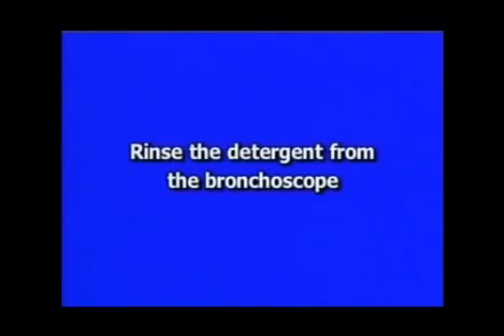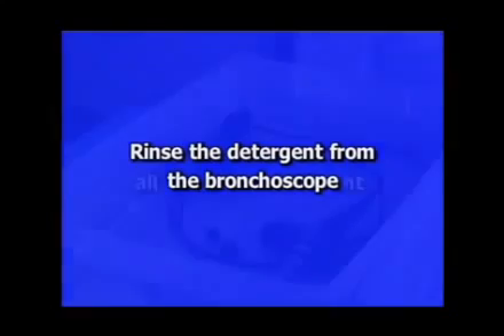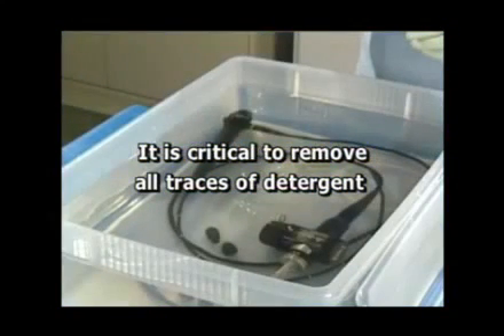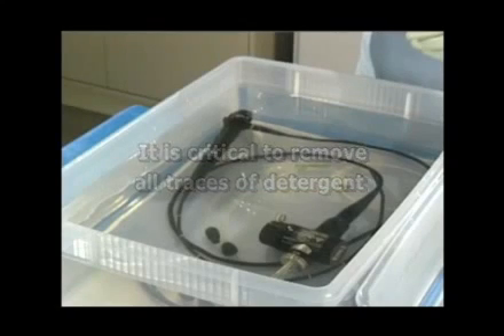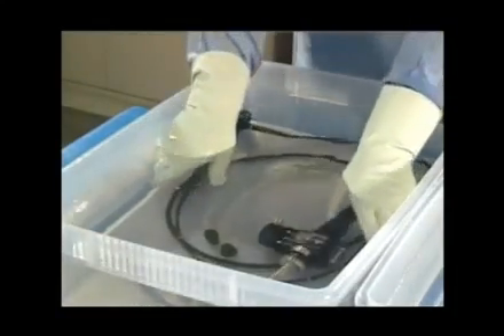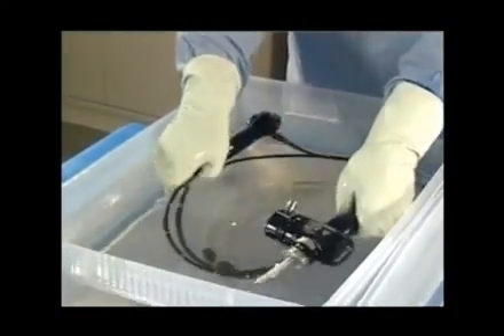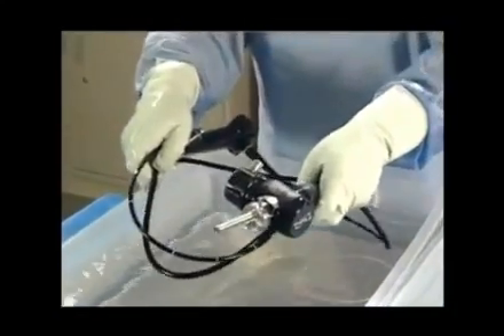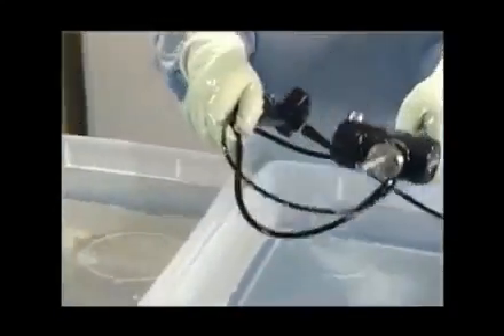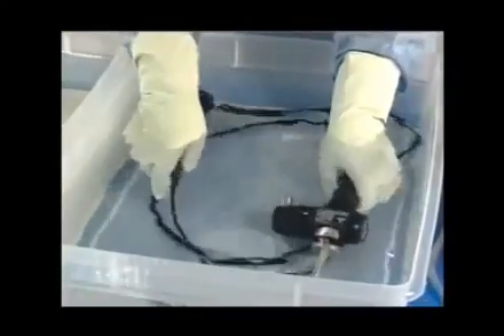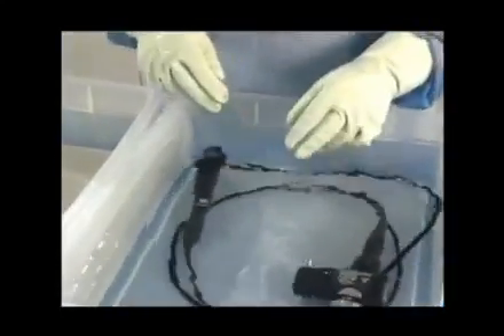The next step is to rinse the detergent from the bronchoscope. It is critical to remove all traces of detergent as it may interact with or inhibit the activity of the high-level disinfectant or sterilant you will use later. Transfer the bronchoscope and accessories to a basin or sink filled with clean water. Disposable cleaning brushes will be later discarded.